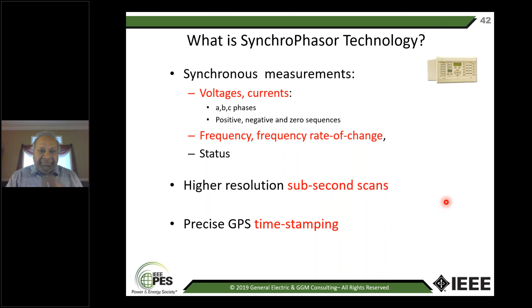So what is synchrophasor technology? The synchronous measurements: the voltages, currents, ABC, positive, negative, and zero sequence, frequency and rate of change of frequency, and also some status information. It's higher resolution, sub-second scans. Remember, SCADA is every 2 to 4 seconds, and this is every few milliseconds, 30 milliseconds or so. And more importantly, they're all timestamped. So you know precisely when the measurement was taken, unlike SCADA, which does not have timestamps. So the real-time grid measurements will be much faster.